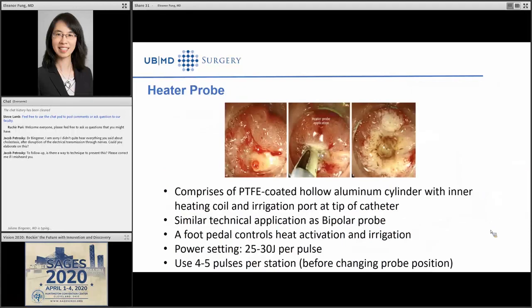This is the heater probe, which we're going to touch on very briefly. It's almost similar to the bipolar probe in that it's also a contact device, and you need to apply it directly to the tissue. It's made of PTFE, as it's thought that because of this, it won't stick to the tissues after coagulation. It has an inner heating coil and an irrigation port at the tip of the catheter, so you can irrigate the area after coagulating. You use a foot pedal to control heat activation and irrigation, and you want to use 4 to 5 pulses per station.